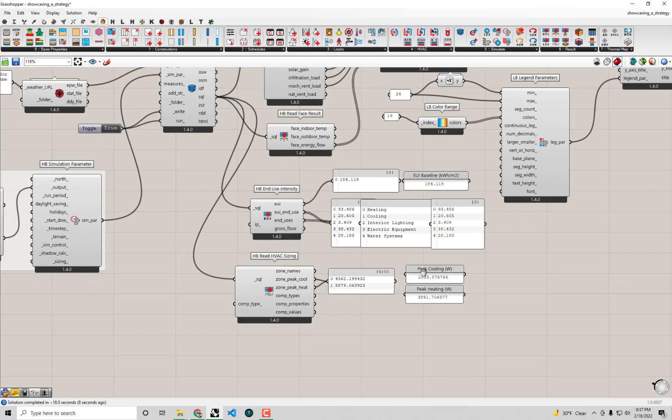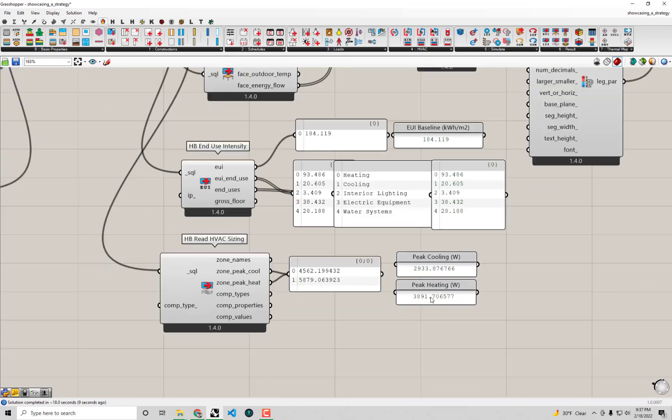Lo and behold, it looks like our retrofit does have a pretty significant impact on the size of the cooling and heating system. In fact, in terms of the cooling system, it looks like we could reduce the size of the air conditioner we need for a building like this by almost half, thanks to sealing the building up and reducing that infiltration and improving that insulation.